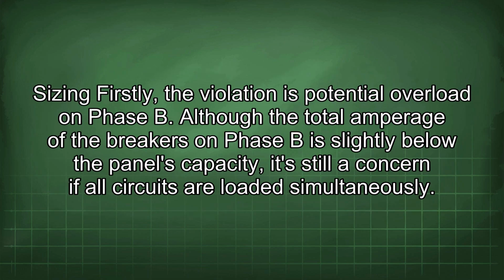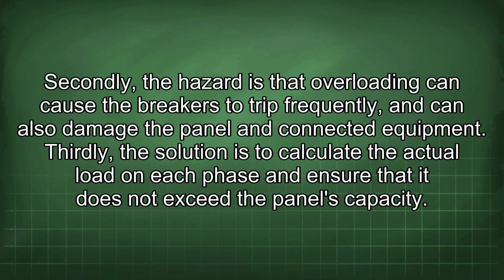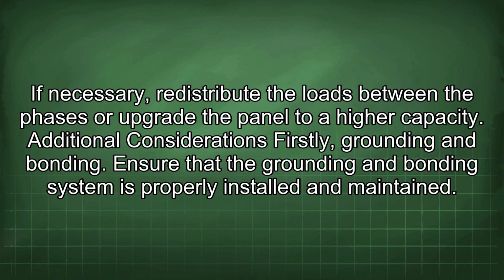Sizing. Firstly, the violation is potential overload on phase B. Although the total amperage of the breakers on phase B is slightly below the panel's capacity, it's still a concern if all circuits are loaded simultaneously. Secondly, a hazard is that overloading can cause the breakers to trip frequently and can also damage the panel and connected equipment. Thirdly, the solution is to calculate the actual load on each phase and ensure that it does not exceed the panel's capacity. If necessary, redistribute the loads between the phases or upgrade the panel to a higher capacity.